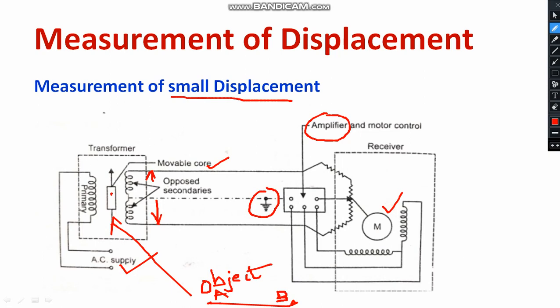With respect to the displacement, as the core starts moving, the output voltage of the transformer gets varied. That output is amplified with the help of a suitable amplifier, because the signal may be very small. The amplifier output is directly connected to the motor, and thereby the motor starts operating. The change in displacement is directly proportional to the output voltage, which directly depends on the motor movement. This way you can figure out small displacement in a simple manner.